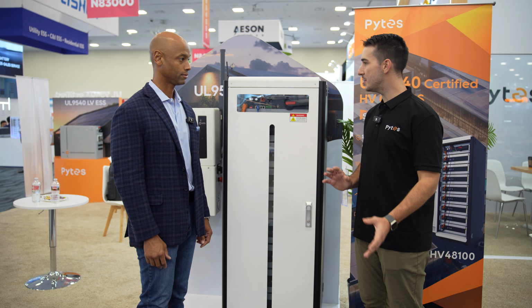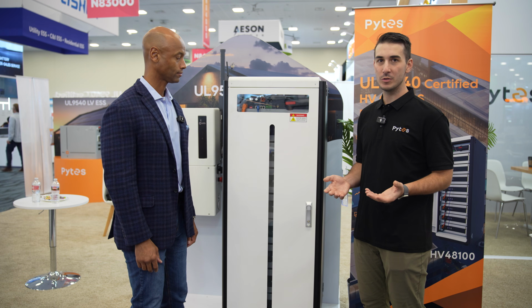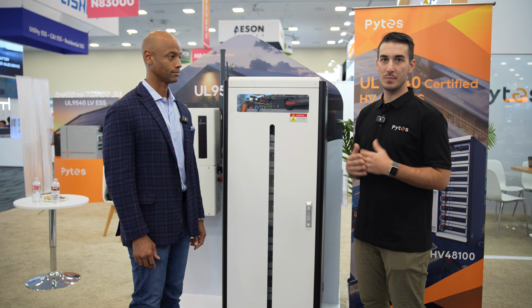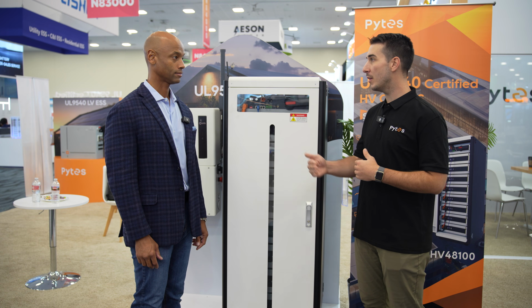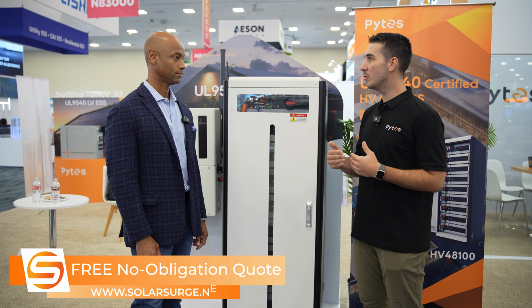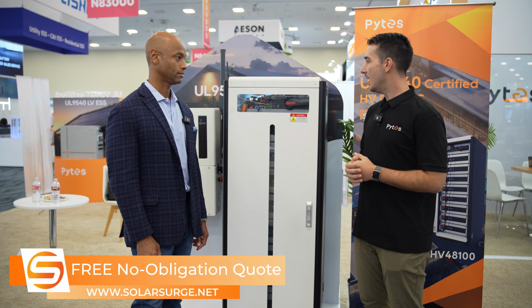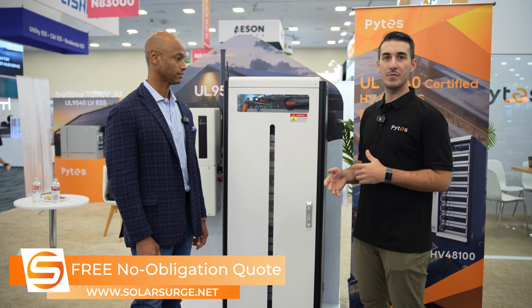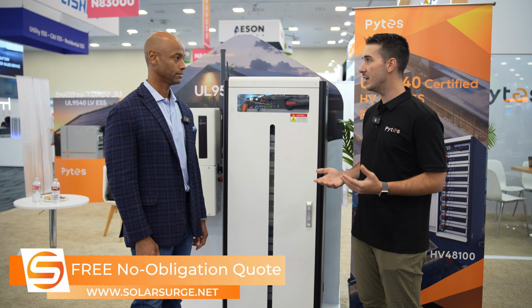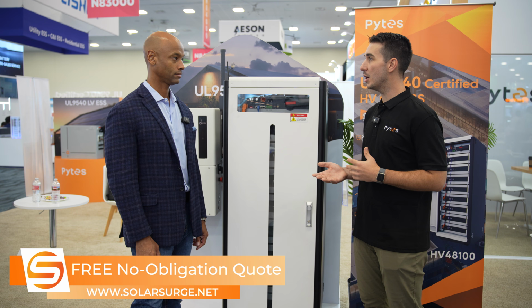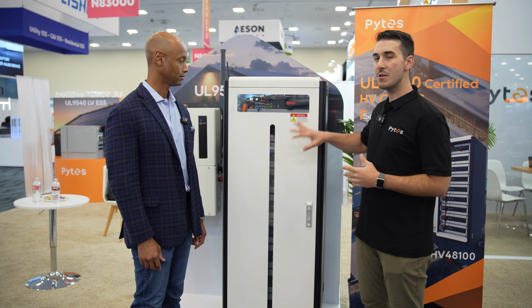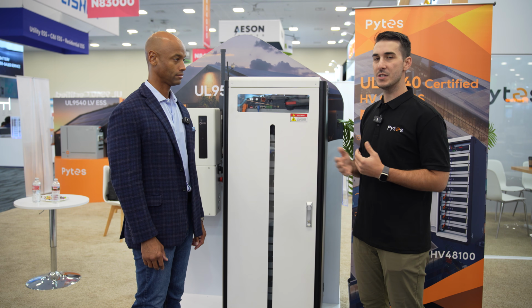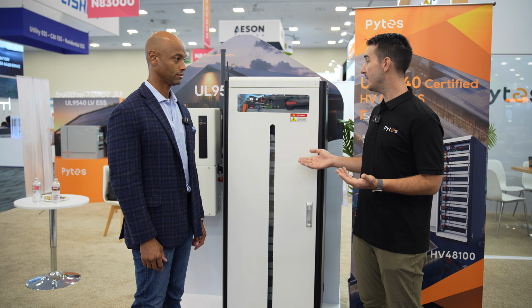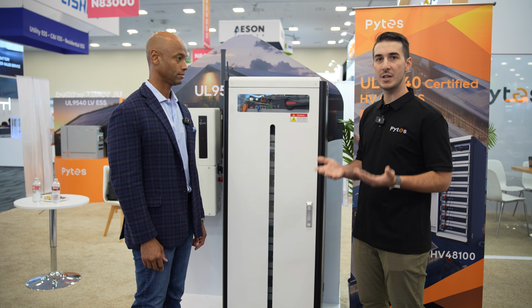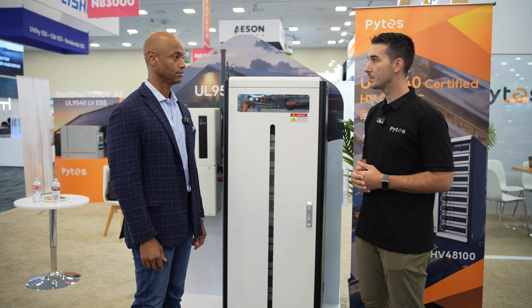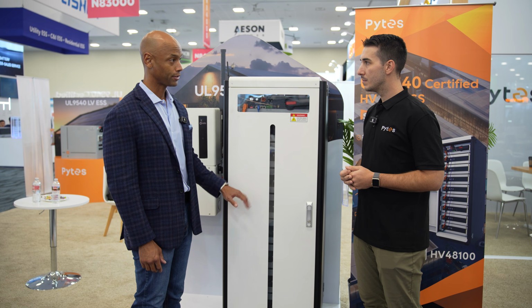Yeah, so this differs quite a bit from the 48 volt nominal solutions most of us are already familiar with, where we just parallel batteries at that same nominal voltage until we reach our desired capacity. This is a bit different. So now instead of parallel connecting batteries to maintain that 51.2 volts or 48 volt nominal DC input, we're now series connecting the batteries instead. So this is going to get us into a voltage range, in this case, between 200 and 900 volts DC. And you achieve that by series connecting individual battery modules. Correct.